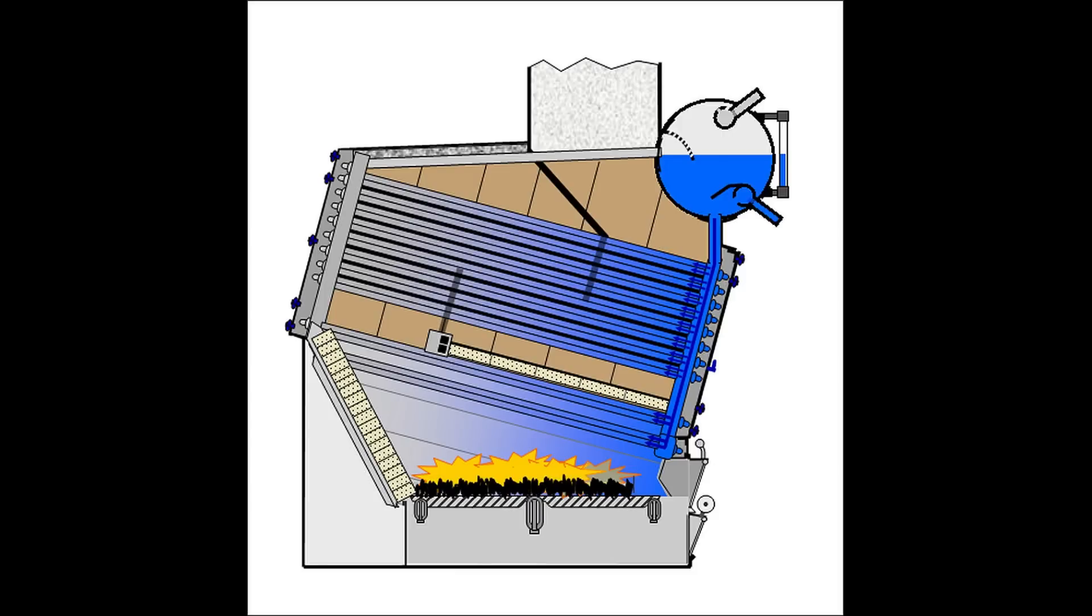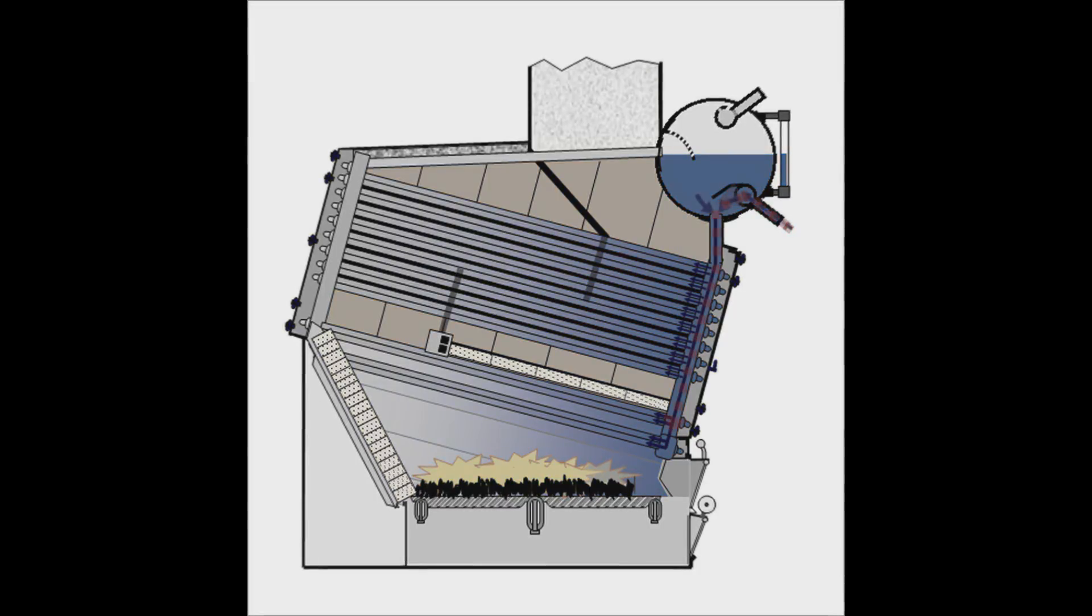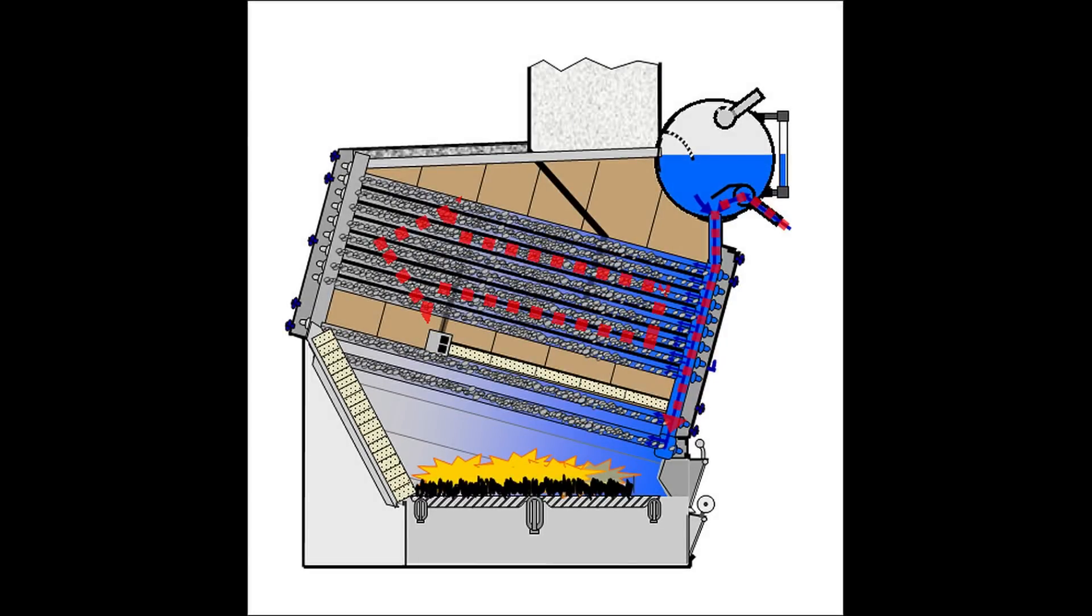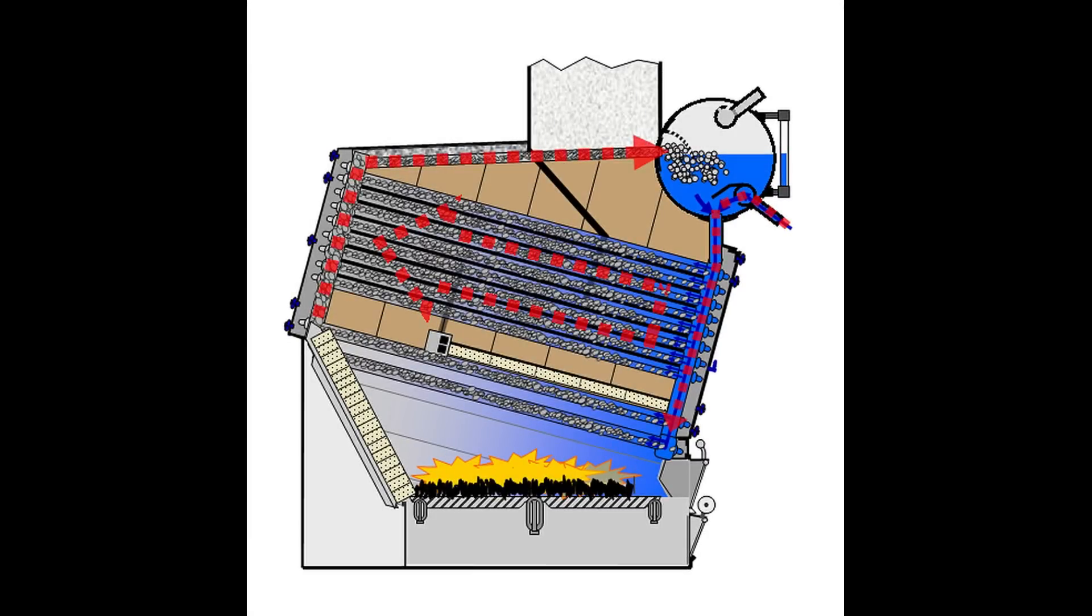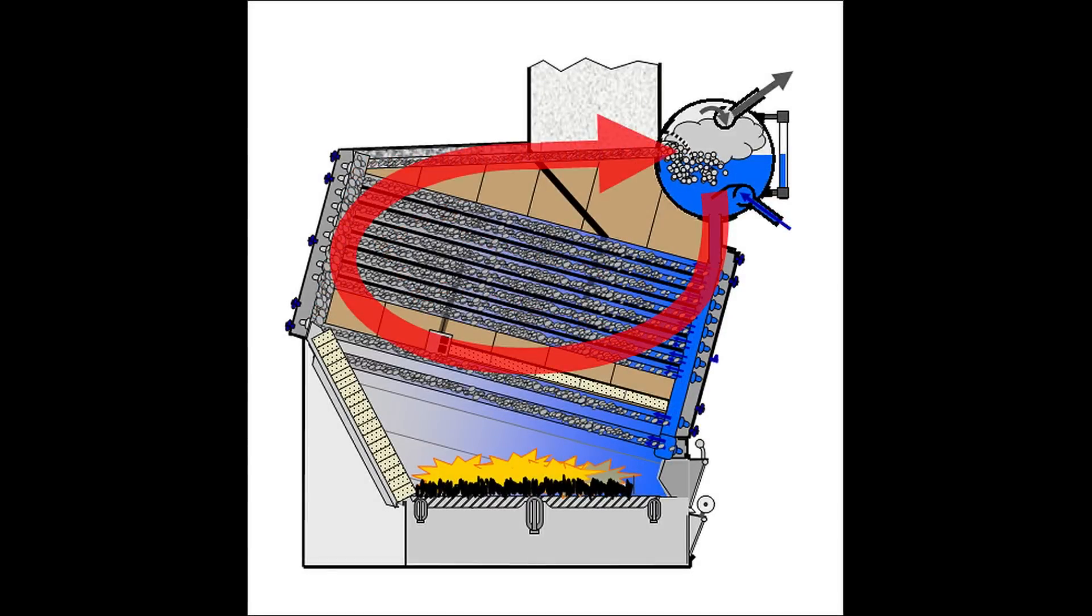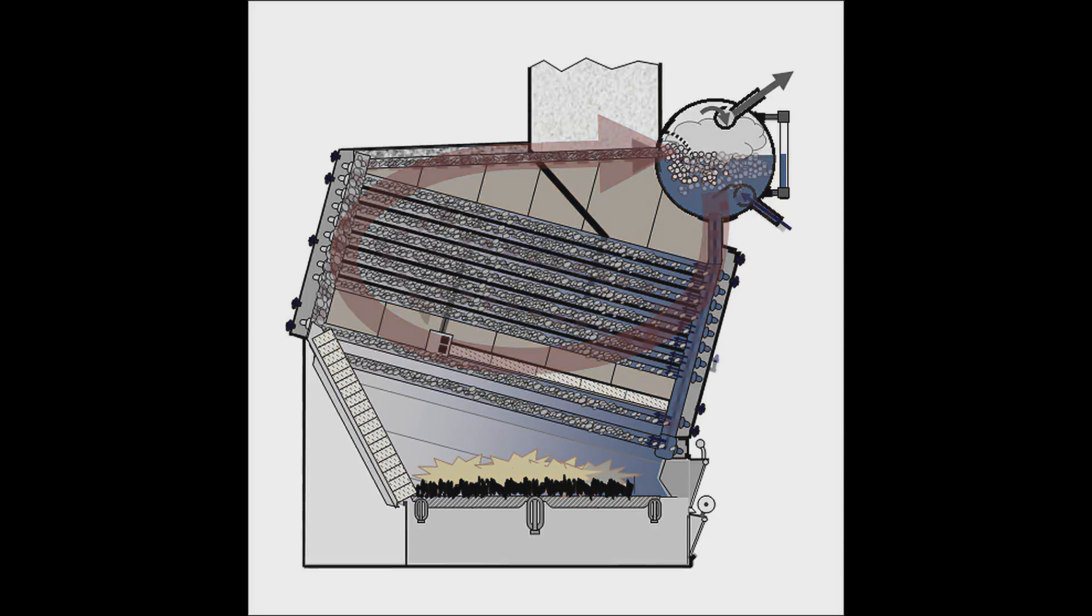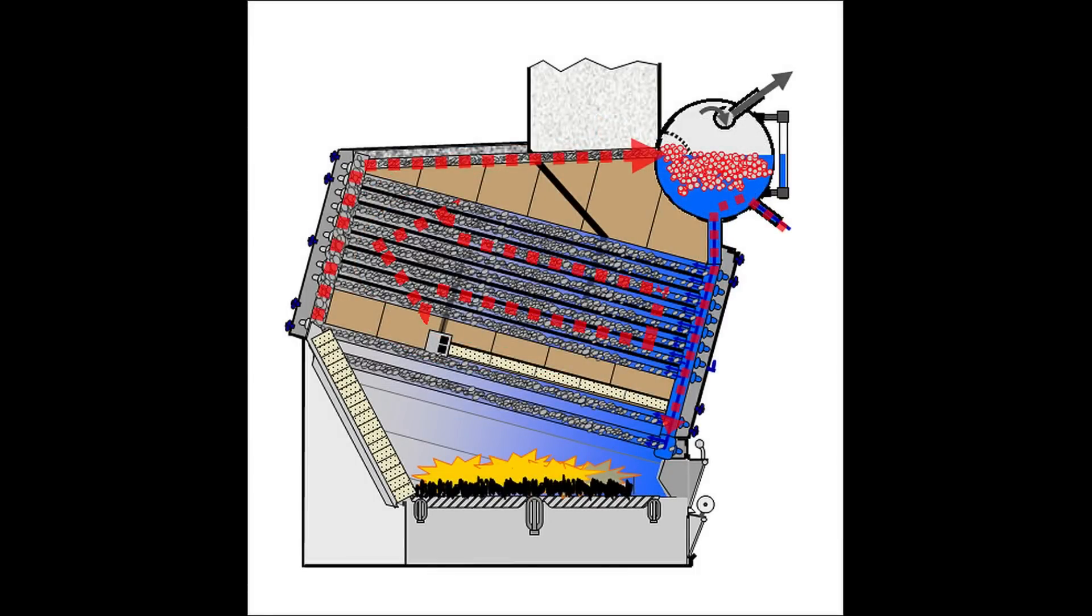So that's how heat moved, but what about water and steam? It started with feed water preheated almost to boiling point and injected into the steam water drum. That kept it from condensing freshly made steam and reduced thermal shock to hot metal parts inside the drum. Once inside the drum, water was directed toward the lower tube headers by a baffle and from there into the water tubes. Conversion of water to steam occurred along the length of the tubes. As it expanded and turned into steam, the 15 degree upward tube tilt caused it to rise from the low end and into the upper headers through which it passed into rows of large circulating tubes at the top of the boiler. From there, the steam spewed from the tubes into the water steam drum completing the loop. As it shot into the drum, steam was directed downward by another baffle to reduce splashing in the space at the top of the drum. It then rose and separated from the water where it entered the dry pipe that ran along the top of the drum's full length.